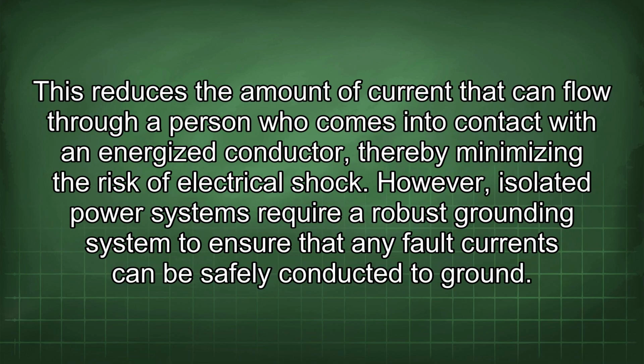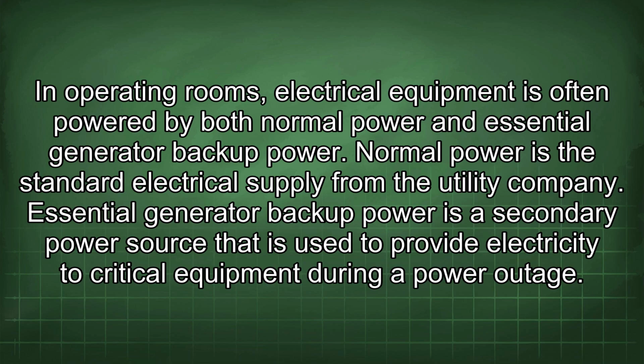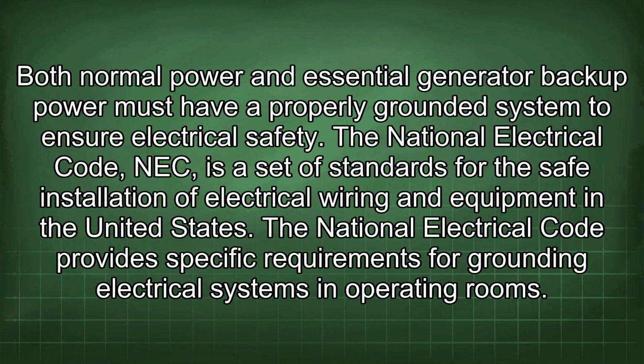This reduces the amount of current that can flow through a person who comes into contact with an energized conductor, thereby minimizing the risk of electrical shock. However, isolated power systems require a robust grounding system to ensure that any fault currents can be safely conducted to ground. In operating rooms, electrical equipment is often powered by both normal power and essential generator backup power. Normal power is the standard electrical supply from the utility company. Essential generator backup power is a secondary power source that is used to provide electricity to critical equipment during a power outage. Both normal power and essential generator backup power must have a properly grounded system to ensure electrical safety.